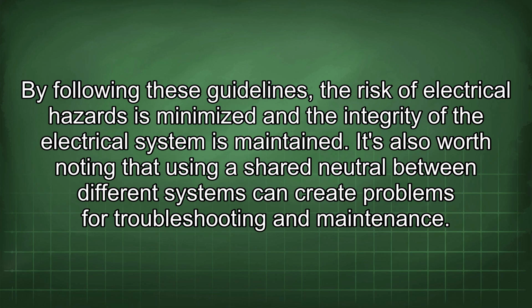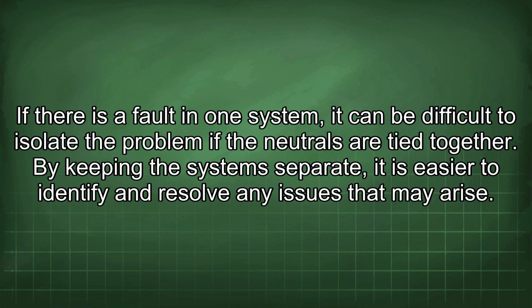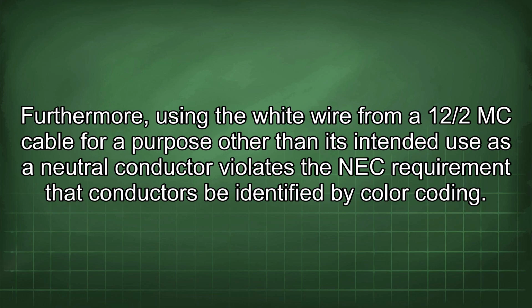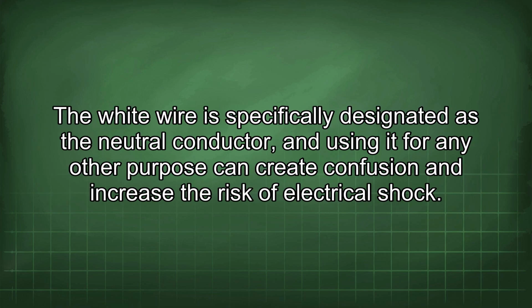It's also worth noting that using a shared neutral between different systems can create problems for troubleshooting and maintenance. If there is a fault in one system, it can be difficult to isolate the problem if the neutrals are tied together. By keeping the systems separate, it is easier to identify and resolve any issues that may arise. Furthermore, using the white wire from a 12/2 MC cable for a purpose other than its intended use as a neutral conductor violates the NEC requirement that conductors be identified by color coding. The white wire is specifically designated as the neutral conductor, and using it for any other purpose can create confusion and increase the risk of electrical shock.